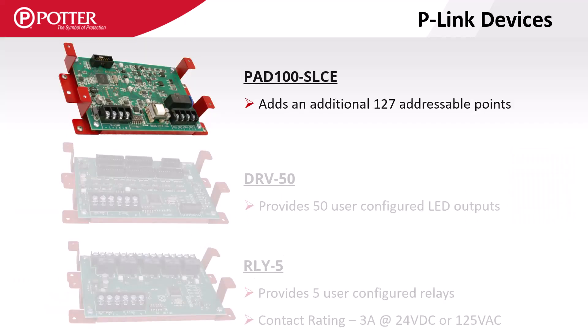The PAD-100 SLC expander card is used with large format panels when more than 127 SLC devices are required. This card is not used with small format panels, since they are limited to the number of SLC devices they can handle.